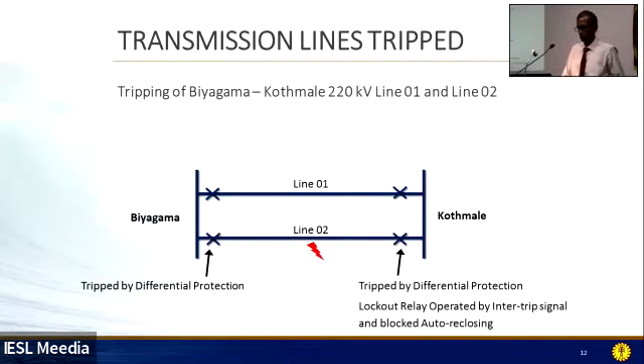Simultaneously, the auto reclosers of the line started their process, and after about 0.8 seconds those auto reclosers were supposed to close the line. But before that, there was an intertrip signal from the Biyagama end to the Kotmale end, and lockout relays at the Kotmale end operated in this line too. For that reason, from the Kotmale end the auto reclosing process could not continue and stopped at that point. However, from the Biyagama end, the line was auto reclosed after about 0.9 seconds. Anyhow, the power flow through line 2 could not continue because of the permanent tripping from the Kotmale end.